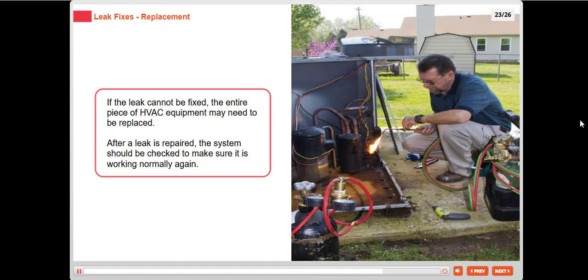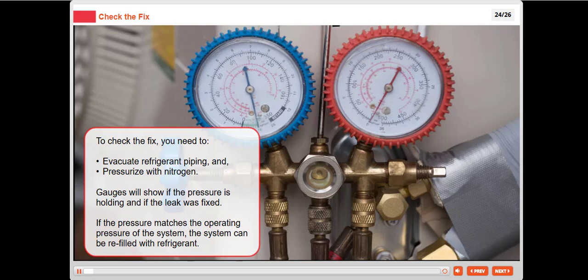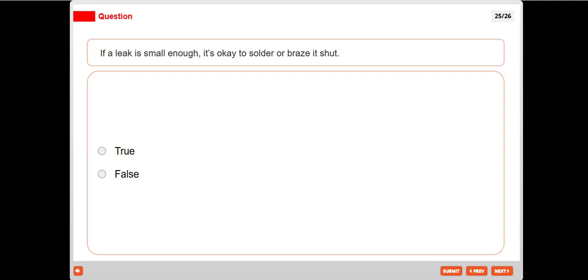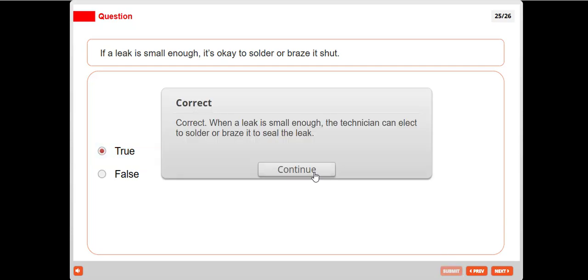To check the fix, you need to evacuate refrigerant piping and pressurize with nitrogen. Gauges will show if the pressure is holding and if the leak was fixed. If the pressure matches the operating pressure of the system, the system can be refilled with refrigerant. If a leak is small enough, it's okay to solder or braze it shut. So I think it's true. In this module, we discuss the causes of leaks and learn how to fix them.